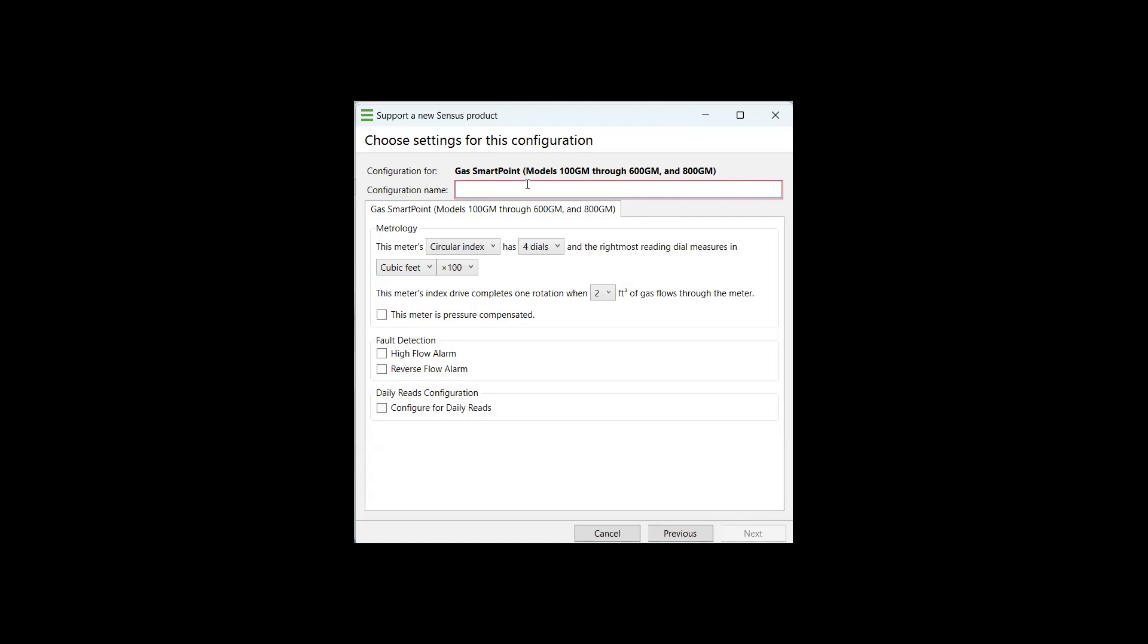The next thing we have to do is give that configuration a name. Since we know that we are going to put this on an R275 meter and only the 100 GM smart point is compatible with that, we're going to call this 100 GM R275. I also like to give it a little bit of nomenclature here with the number of dials and whether or not the meter that you are attaching this to is pressure compensated or not. For this example, it is not a pressure compensated style meter. So we're going to name it 100 GM, R275 with four dials and seven inches, which is seven inches water column, which is the typical delivery or standard delivery pressure of natural gas through R275 meters.